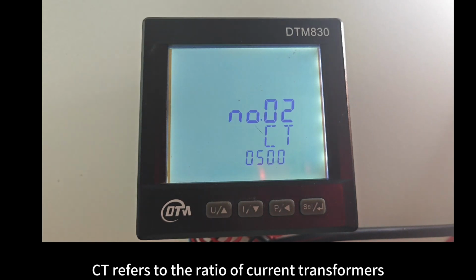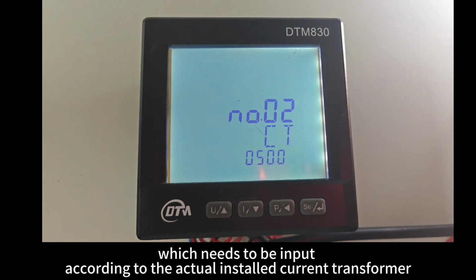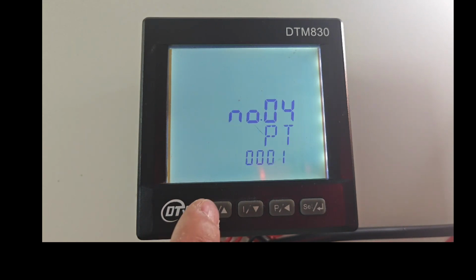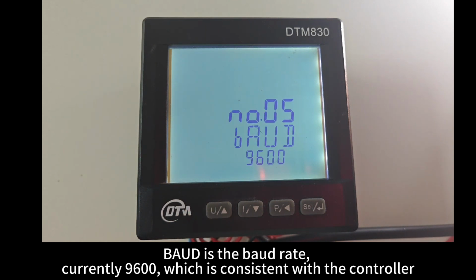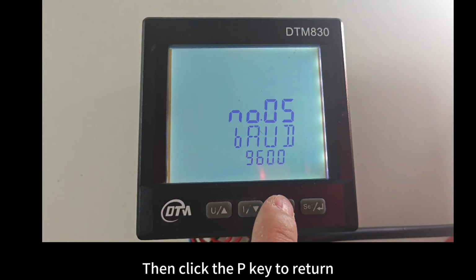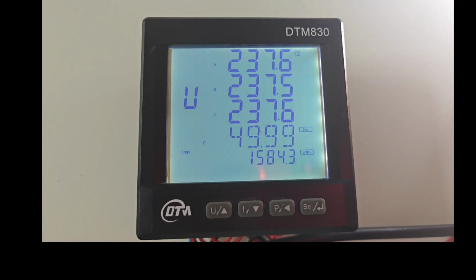CT refers to the ratio of current transformers, which needs to be input according to the actual installed current transformer. Baud is the baud rate, currently 9600, which is consistent with the controller. Then click the P key to return.